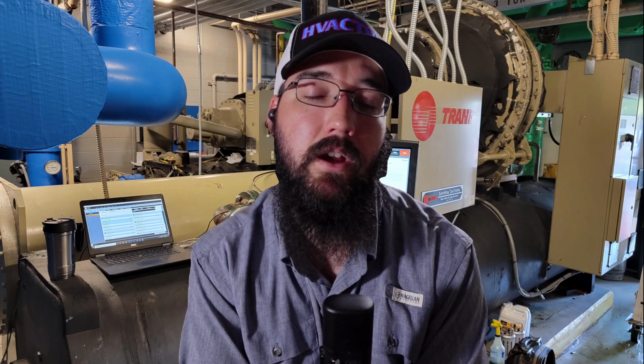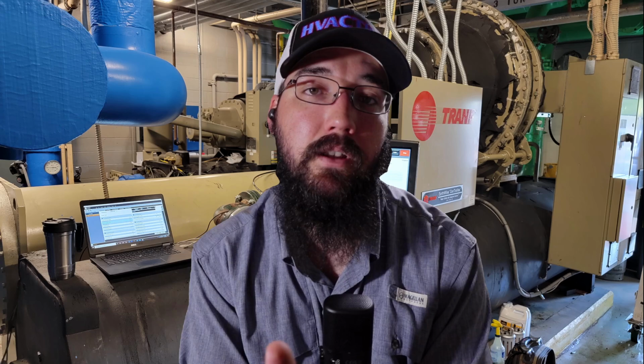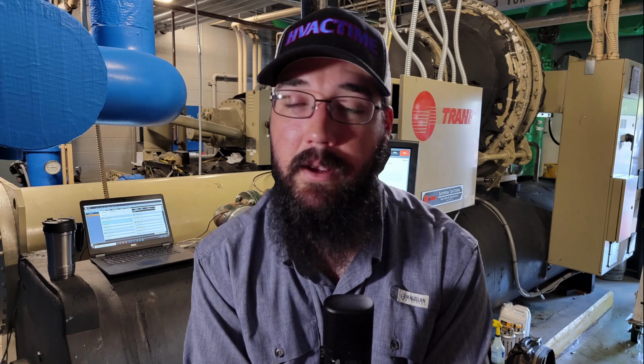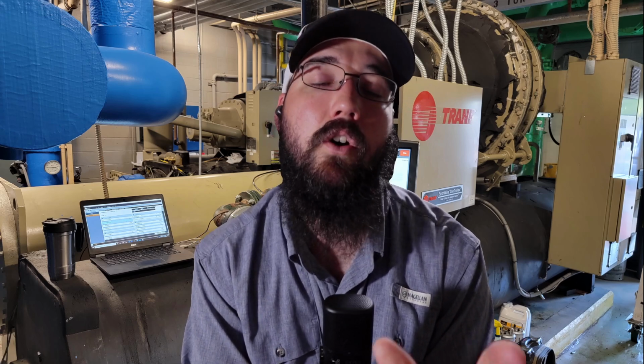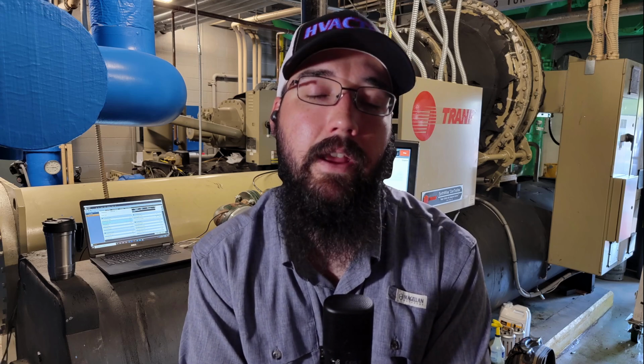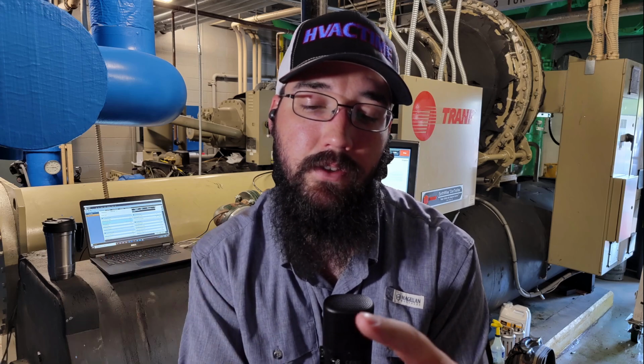So this is something to just be aware of, and it's part of the commissioning process for an EXV. Make sure your polarity is the same. Doesn't matter if it's like for like or not. Always verify the closing and opening direction, and that you have correct polarity. And every valve that I'm aware of on the market, or every controls package, will do that 3-step process: fully closed, fully open, fully closed. That is considered calibrated.